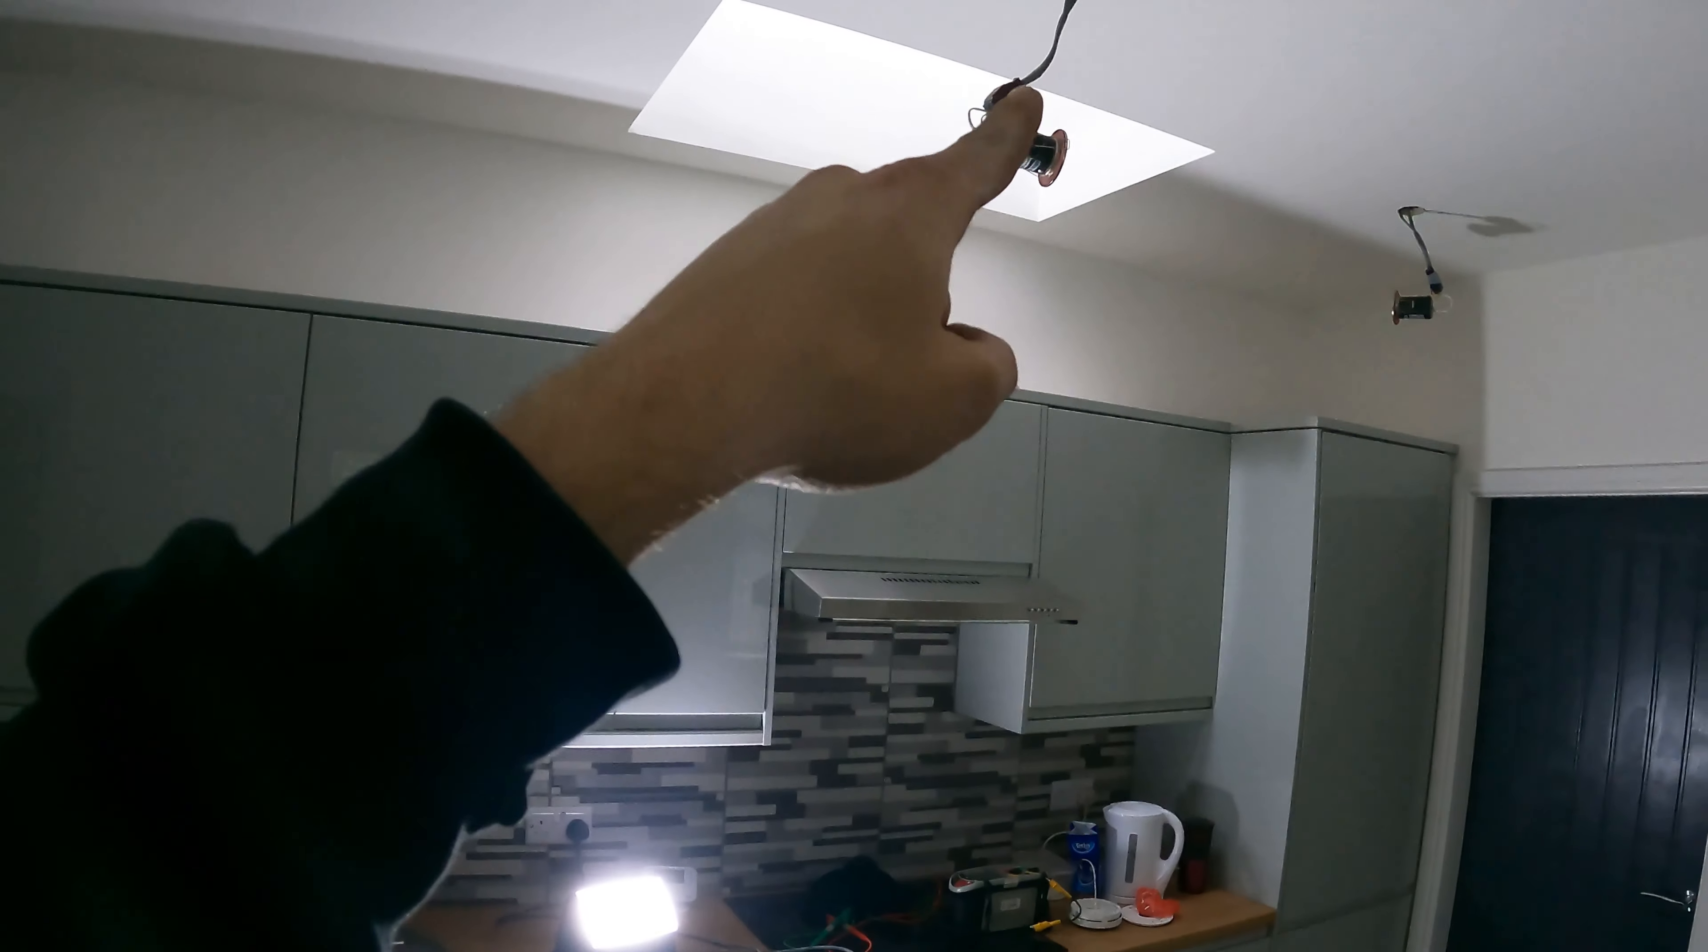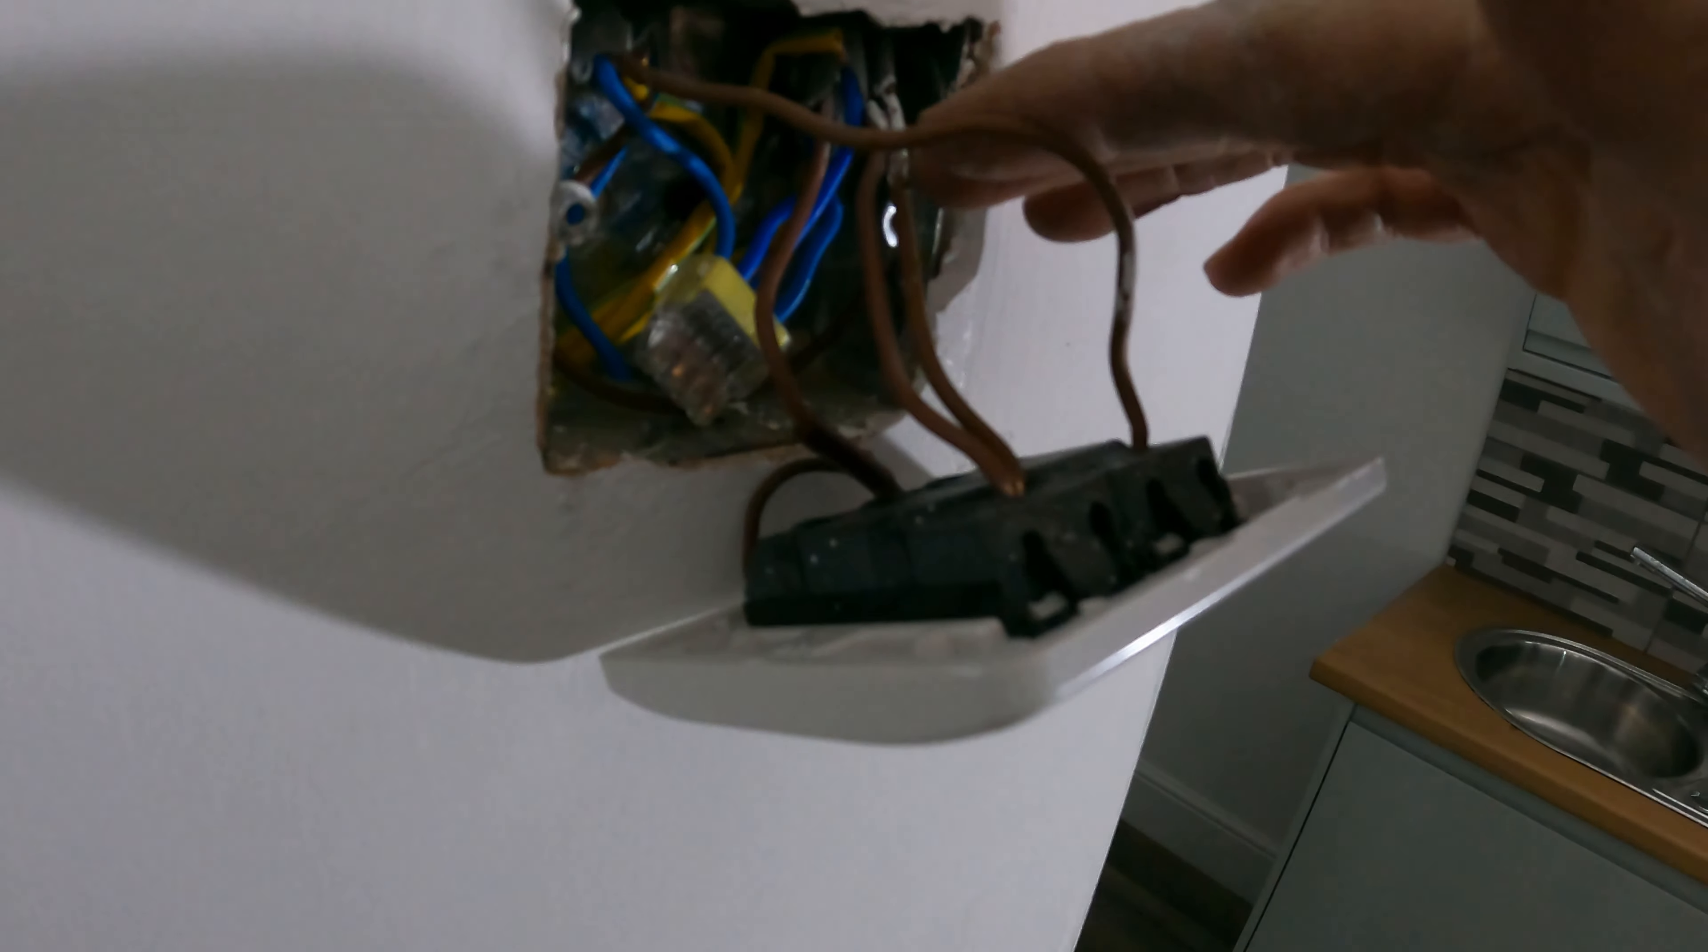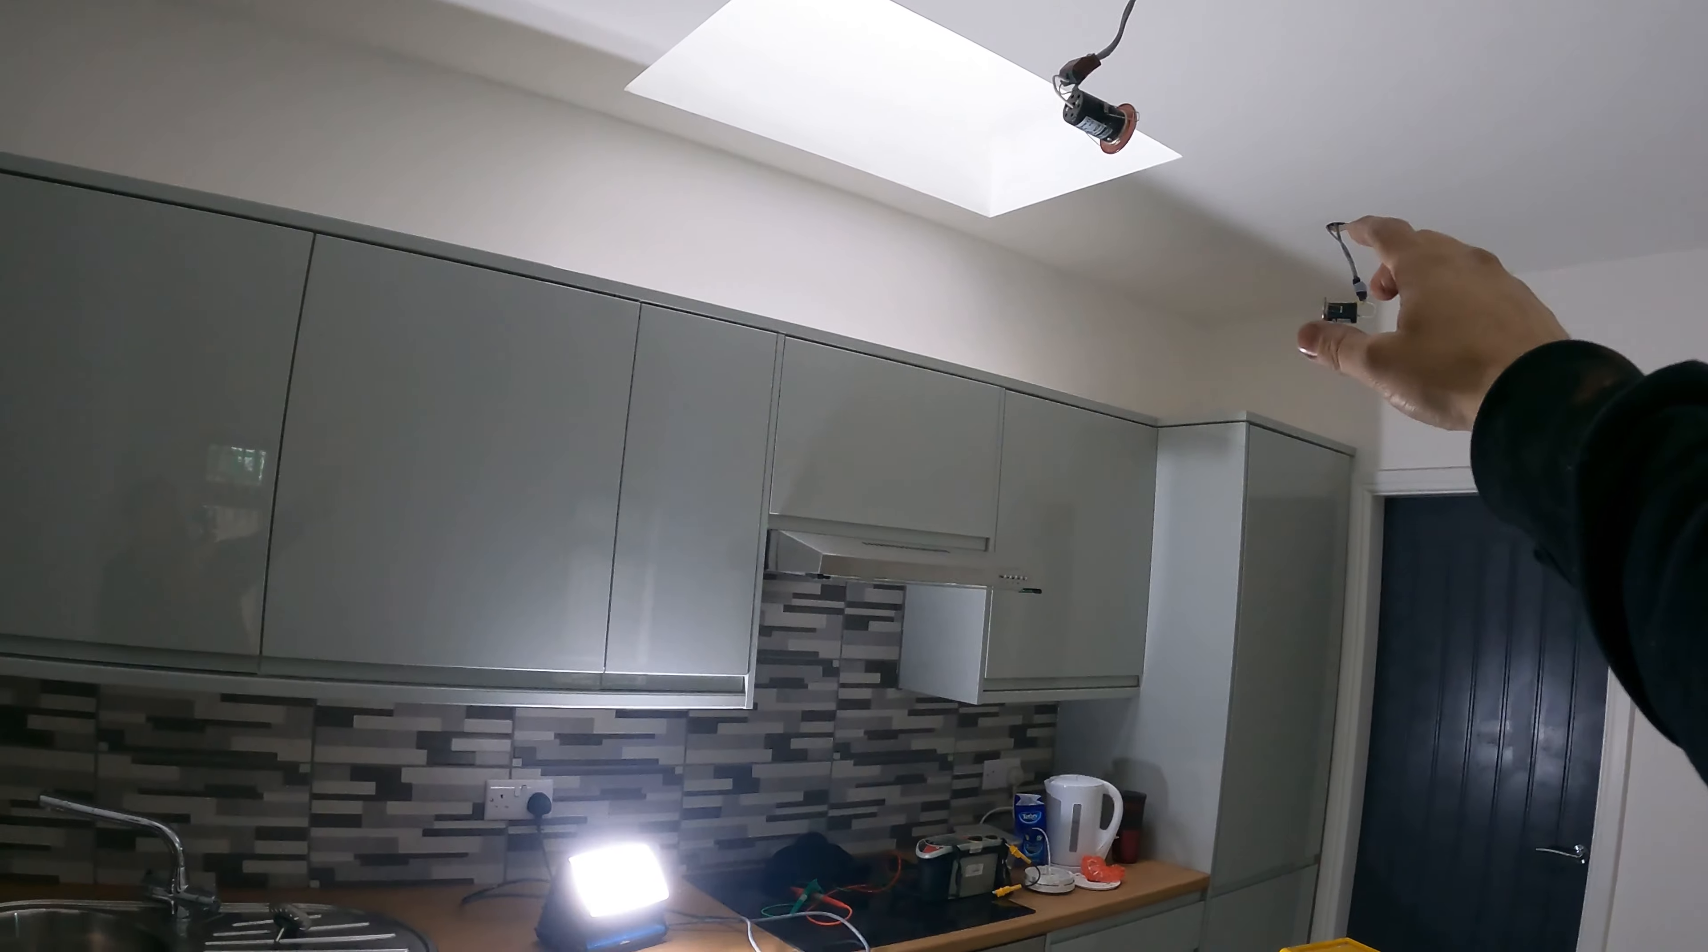And then obviously just sort of spurred off that light to feed the smoke detector, which is obviously wrong because it's switched. So one of these two here, presuming—I'm going to bell it out and check—goes straight from there, straight over to that end light. So I disconnect that, bell it out.